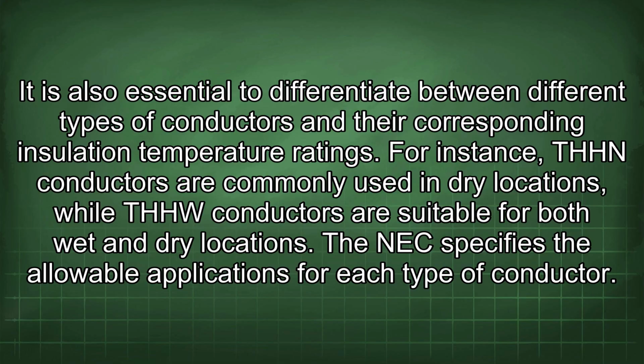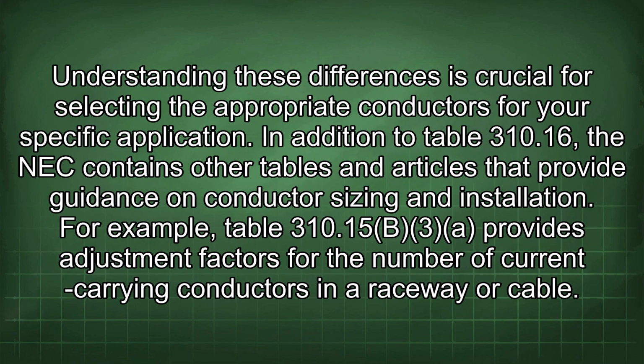For instance, THHN conductors are commonly used in dry locations, while THHW conductors are suitable for both wet and dry locations. The NEC specifies the allowable applications for each type of conductor. Understanding these differences is crucial for selecting the appropriate conductors for your specific application. In addition to Table 310.16, the NEC contains other tables and articles that provide guidance on conductor sizing and installation.